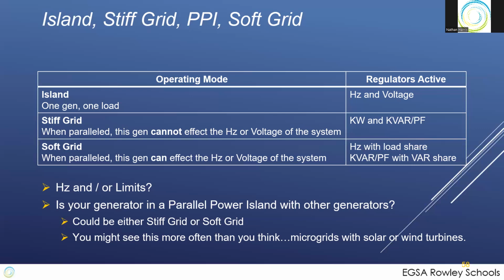Well, on this grid, they couldn't. As soon as they went online with these four gens, they stayed in kW regulated, assuming a stiff grid, and they were on a soft grid. They actually became the grid. So when they told these engines to put out 12 MW, when the load on that island that day was only about 10, they went up in frequency. They closed these new generators on the bus and went up to some frequency level, somewhere around 60, 61 hertz. They pushed all the other generators in the island off on reverse power. So bang, bang, bang, bang, bang, all the small ones went off. They were the only grid. They kept driving themselves up even more because they're told to go to a certain kW level, and it's going to push till it gets there. It took the whole place down on frequency. Close the breaker, bang, bang, bang, all the generators in the island went down. Boom, the big gens went down on over frequency and shut the whole place down.